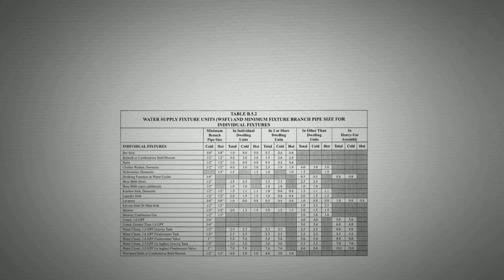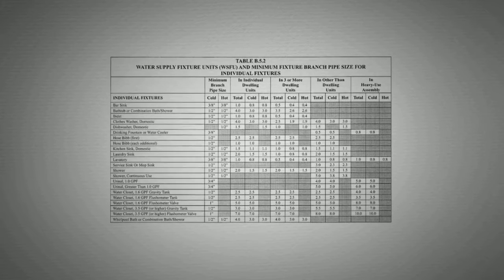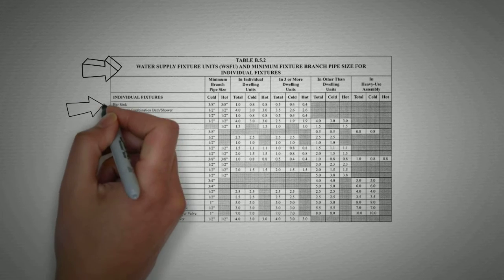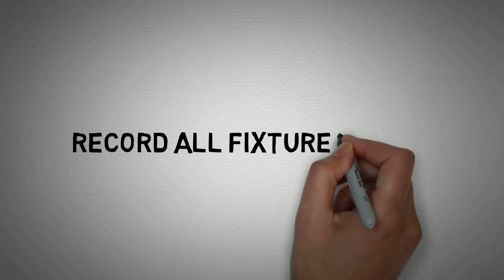First, we're going to list all of the individual fixtures being used in the dwelling unit, building, or assembly. Next, refer to the NSPC's Water Supply Fixture Unit and Minimum Fixture Branch pipe size for individual fixtures table. Use the table and record all of the fixture's unit values.